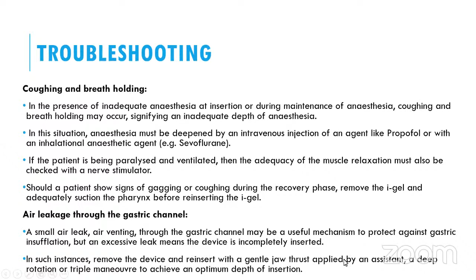Air leakage through the gastric channel: any small air leak, air venting through the gastric channel, may be a useful mechanism to protect against gastric insufflation. But an excessive leak means the device is incompletely inserted. In such instances, remove the device and reinsert with a gentle jaw thrust applied by an assistant, a deep rotation, or the triple maneuver to achieve optimum depth of insertion.